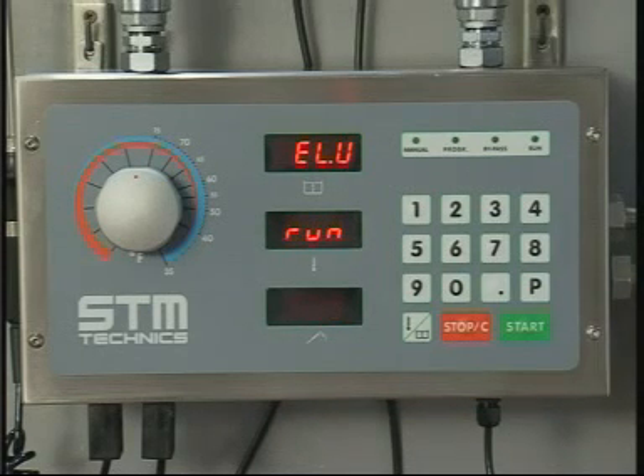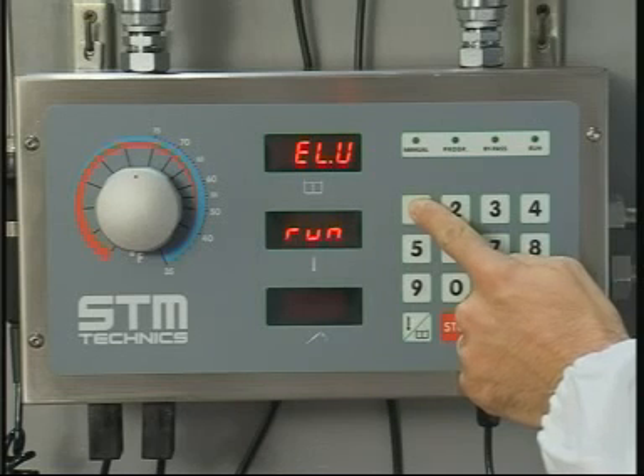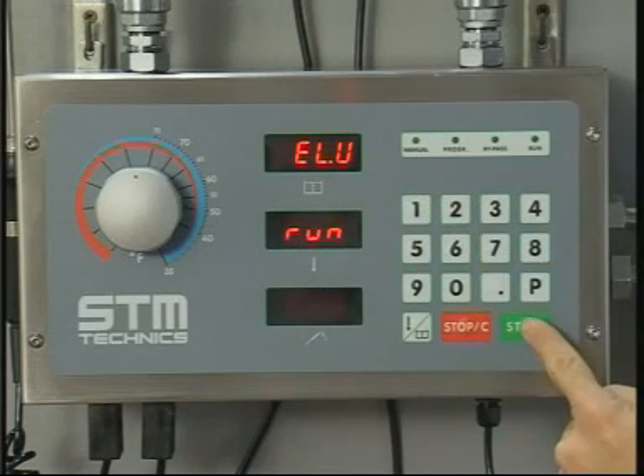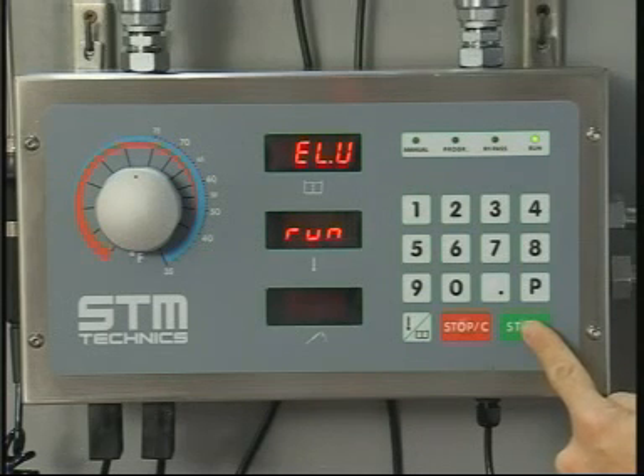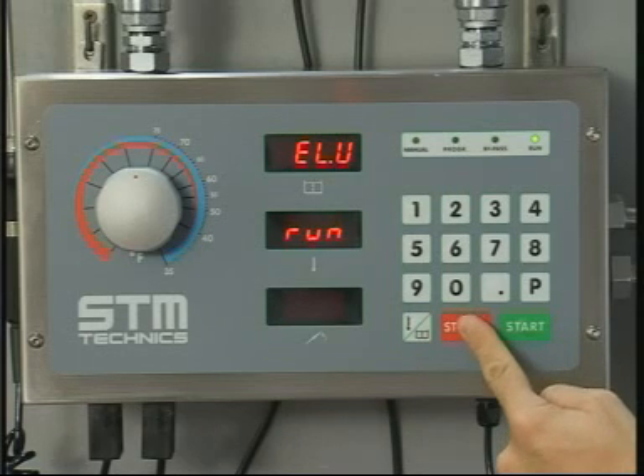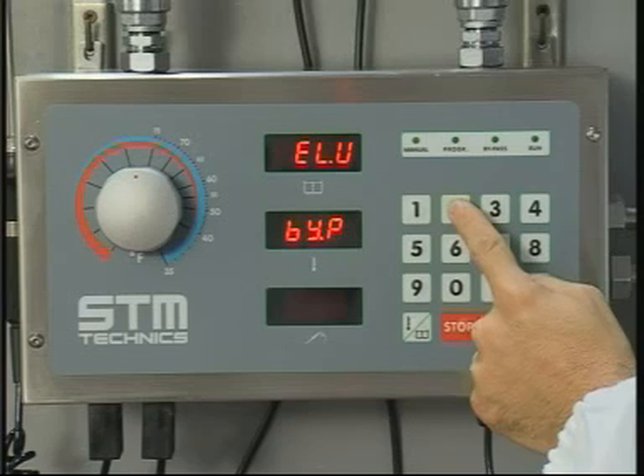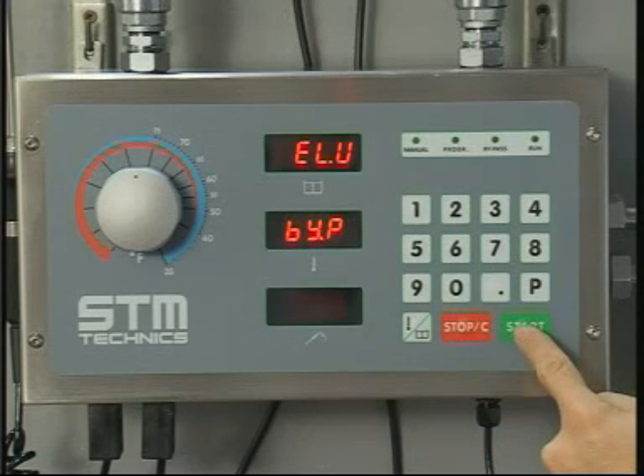ELV run. In this display, it is possible to check independently the main electrovalve and the bypass electrovalve with keys 1 and 2. Choose the desired valve and by pressing start it opens. Pushing stop it closes.